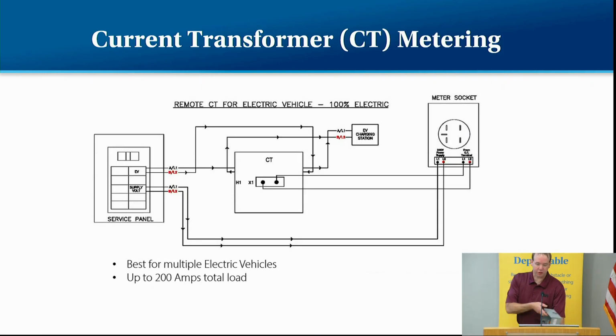So for the current transformer or the CT metering, we'll provide the CT meter box for a small fee. I can't remember what it is off the top of my head. $55. Thank you. So it's a matter of just running wires through the CT. And as you can see by the diagram with the arrows, one wire goes through one way, the other phase goes through the opposite way.